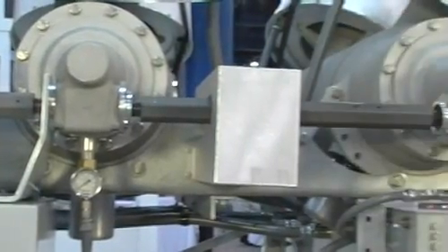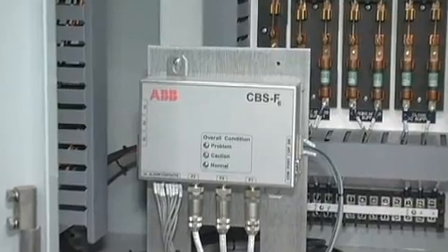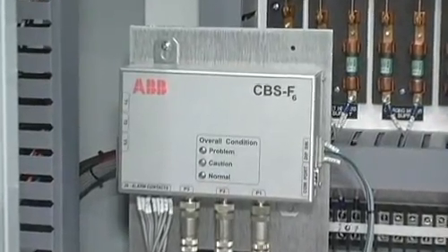So wrapping up what I've just told you, the EPA's mandatory regulation and monitoring of SF6 gas losses amongst utilities is going to happen in 2011. And if you follow the 3 recommendations of eliminating plumbing, providing rigorous testing during manufacturing processes, and also providing some type of monitoring device on SF6 gas systems, it will go a long way to reducing or eliminating SF6 gas losses in your breakers.